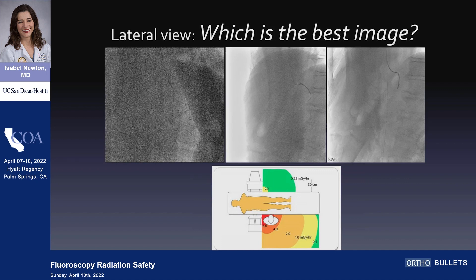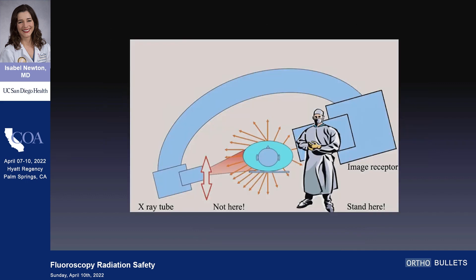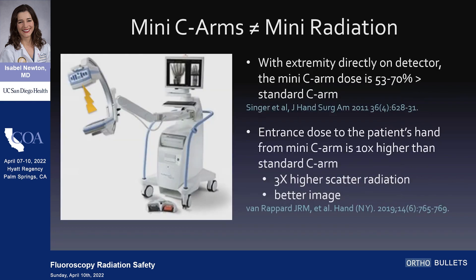People think, oh goodness, you have the source pointing right at you — but that's not how it goes because the patient eclipses most of the photons. I always get questions about mini-C arms. Mini-C arms are not mini-radiation. If you look at the similar geometry, mini-C arms provide better images, but it's at the cost of more radiation and more scatter.